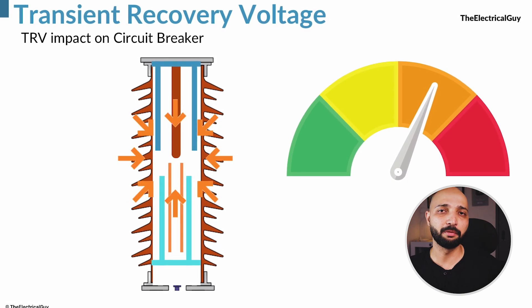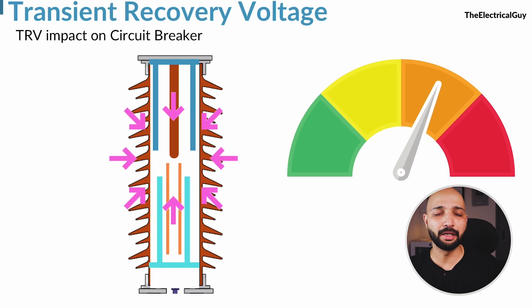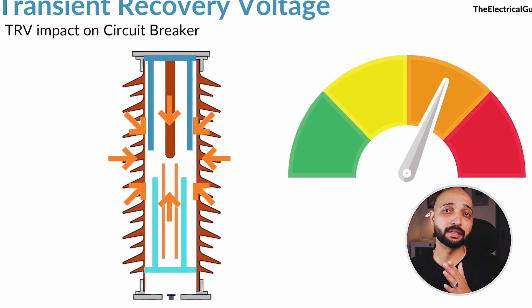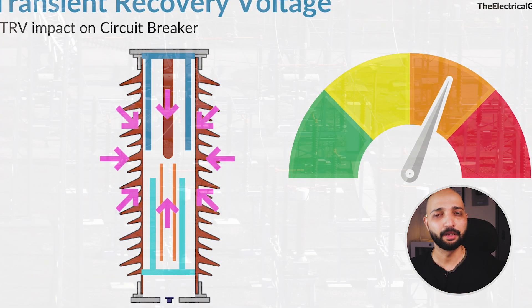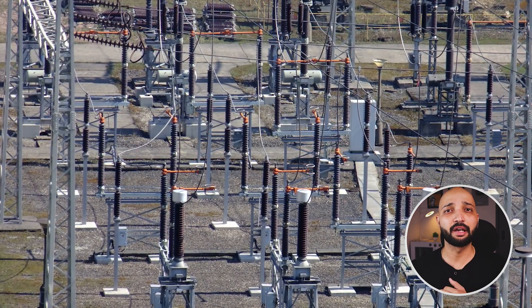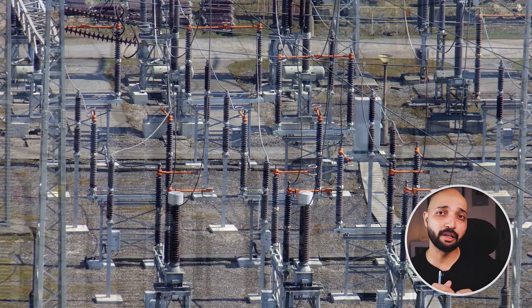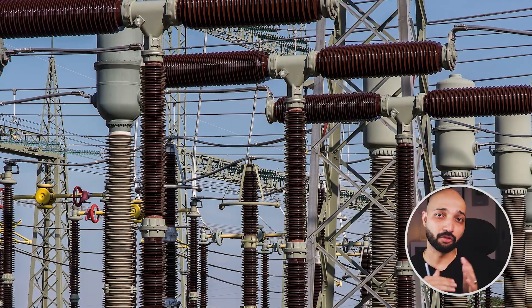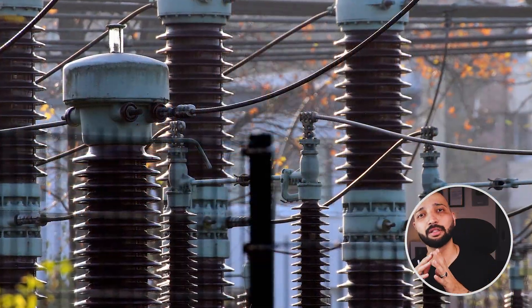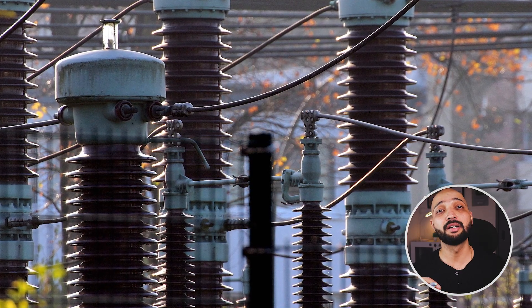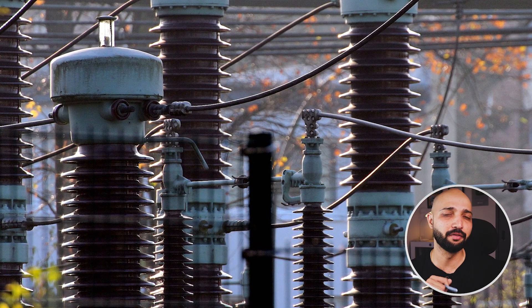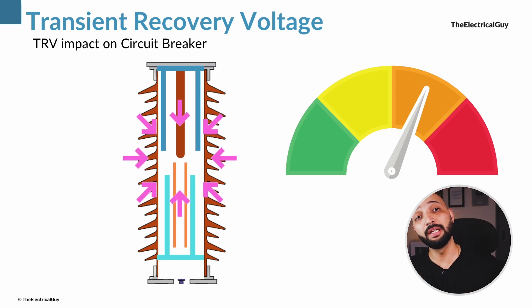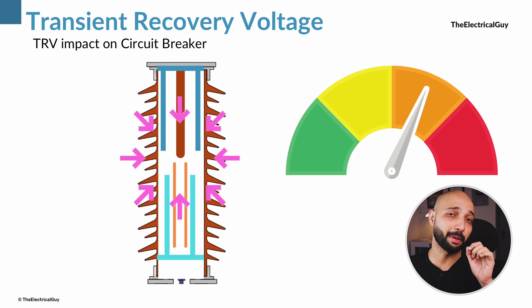Re-strike is a very dangerous situation. It can damage the circuit breaker completely and also damage other equipment in the substation. Therefore, the circuit breaker must be capable of withstanding high TRV and clearing the fault. Different standards like IEC and ANSI have defined different fault situations and TRV values on which the breaker must be tested to prove its capabilities. Circuit breakers that pass all tests under conditions defined by the standards are considered capable of handling the different TRVs that may occur due to different faults, making consideration of TRV while designing the circuit breaker of paramount importance.